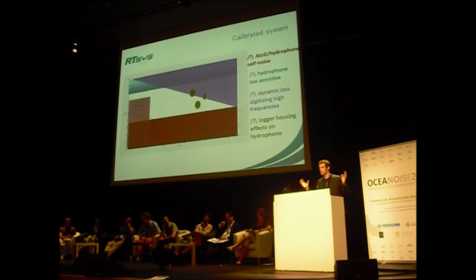If you use a numerical gain, it can give you the feeling that you have a really nice sensitivity, but the truth is you might lose high level noise measurements by just increasing the self-noise of the system. And if your system is not resistant to what we call blocking signals—imagine you've got a sonar speaking very loud at 40 kilohertz—how might that affect my system, and will it still be able to record the other noises?